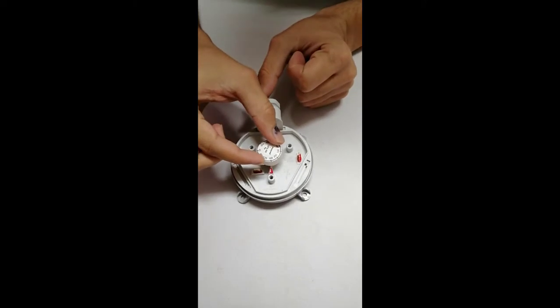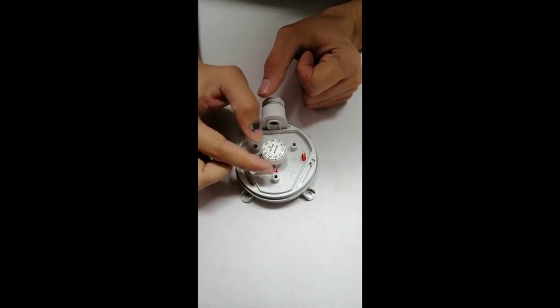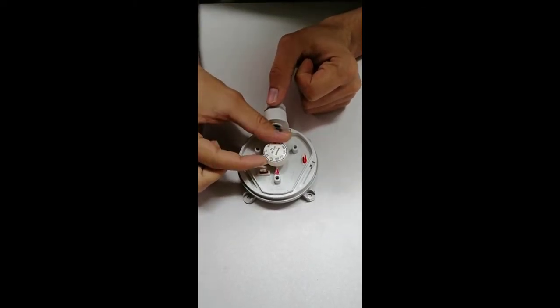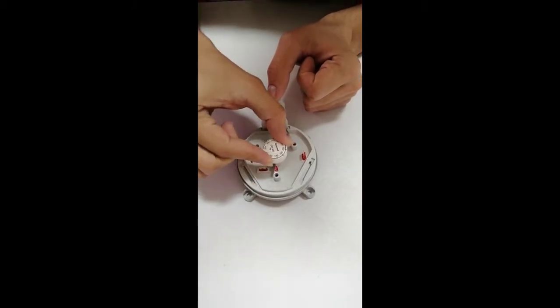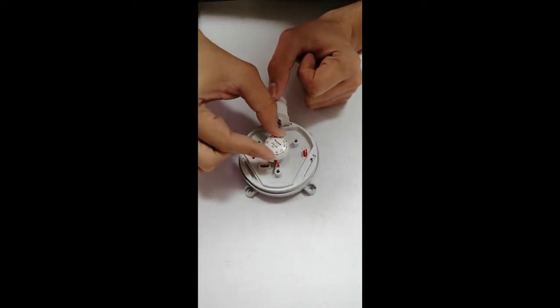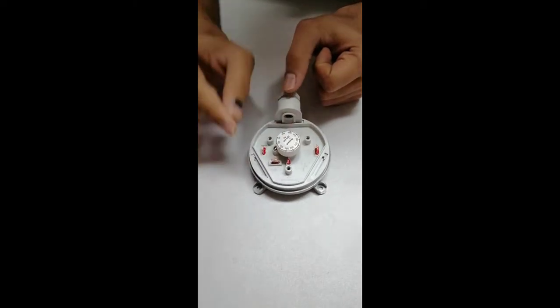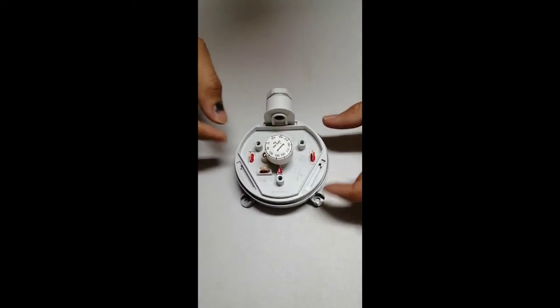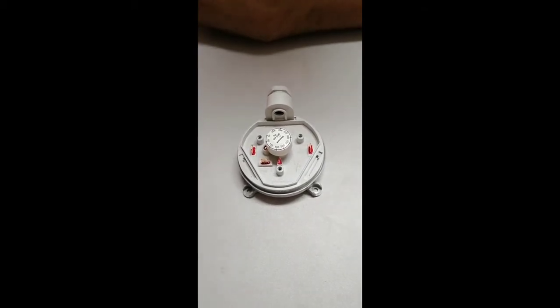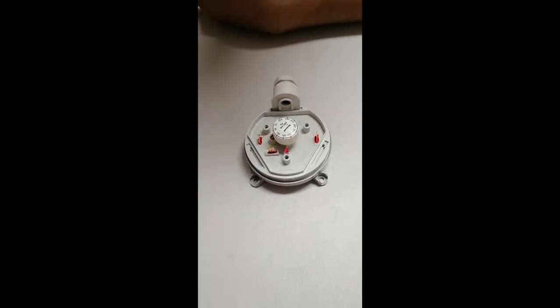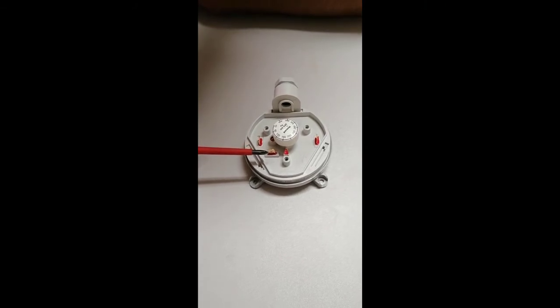Here we have set point dial. Using this dial we can set the differential pressure set point. Okay, so here is the knob. Now it is set to 40, so we can increase up to 400 pascal. So when differential pressure between two ports will increase, then this set point, then it will give us a dry contact signal. Here we have three connection points.